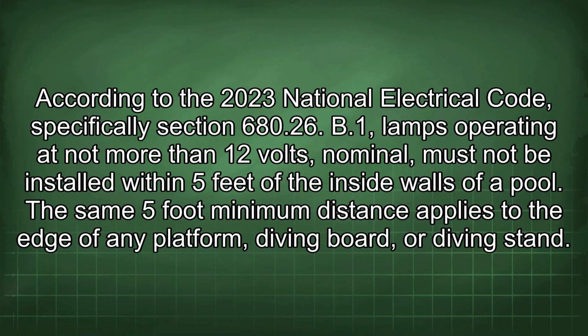According to the 2023 National Electrical Code, specifically Section 680.26, low-voltage lamps operating at not more than 12 volts nominal must not be installed within 5 feet of the inside walls of a pool. The same 5-foot minimum distance applies to the edge of any platform, diving board, or diving stand.